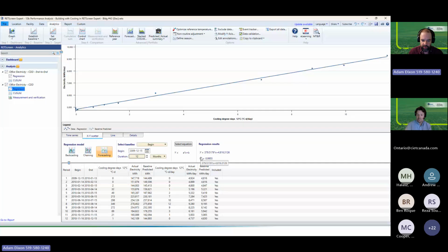And the reason this happens physically, I'm talking a lot of statistics here, is that before, when we have all 38 points, we have the energy consumption driven by weather with an old lighting system, which adds more heat into the building. So your cooling systems have to work a little bit harder, and your heating systems have to work a little less hard in that situation. As well as the post-retrofit conditions where the heat balance is then changed. If you go from halogen lights to LEDs, you've now removed heat in that building.